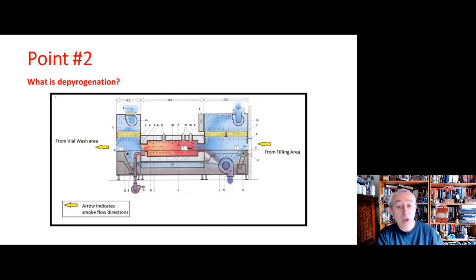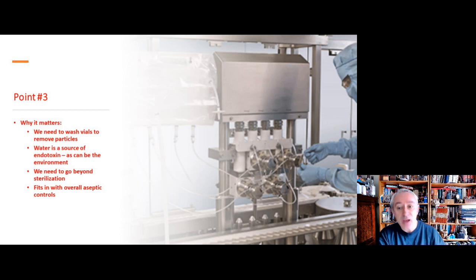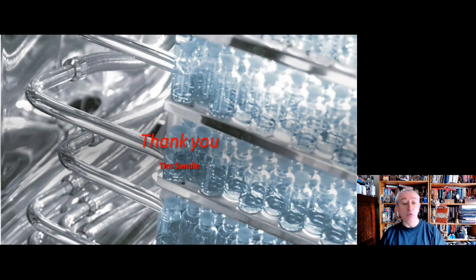That's point number two. Point number three is, well, why bother? Why does all this matter? We have to wash vials to get rid of particles, but then we end up with wet vials. The water, though it's well controlled, could be a source of endotoxin. You've got occasional handling and then the general environment where you get dust particles in particular, which can also have endotoxin on them. So we need to make sure that we are getting rid of the pyrogens - we are depyrogenating and sterilizing the vials as they go through the tunnel. We need to take this principle beyond sterilization, and this fits in with our overall aseptic controls. We want to have vials that, as we're filling them, we know the vials themselves are suitable for a product that is going to be injected into the patient.